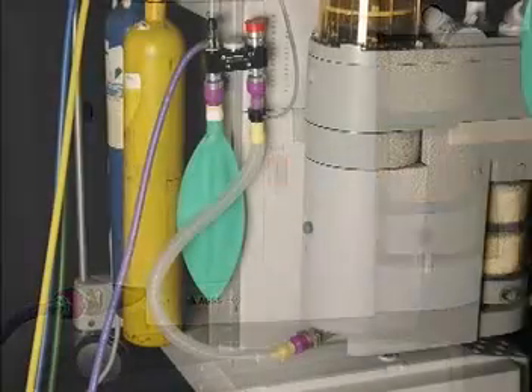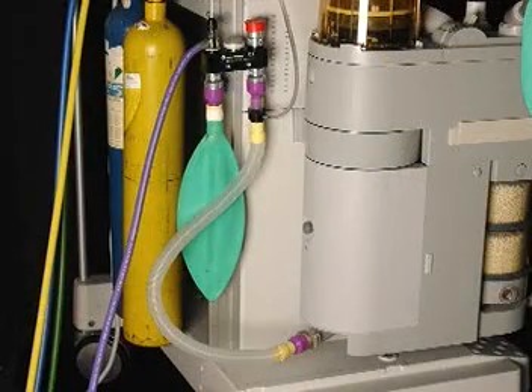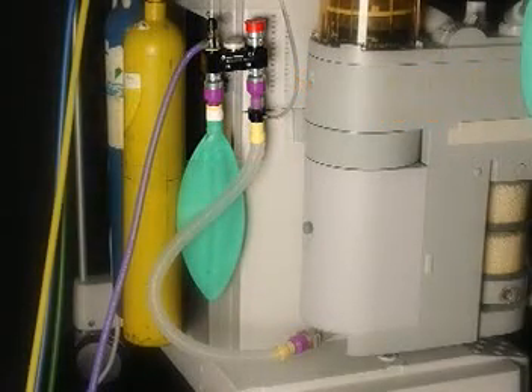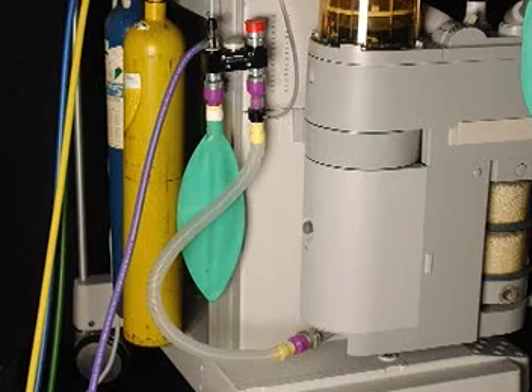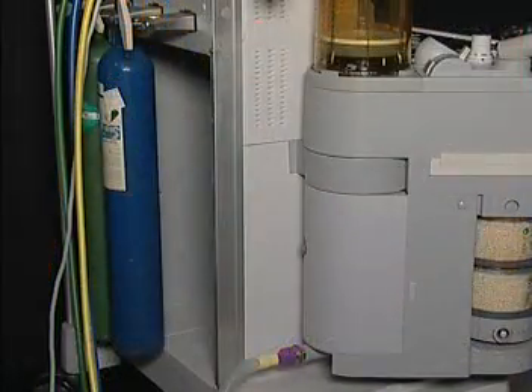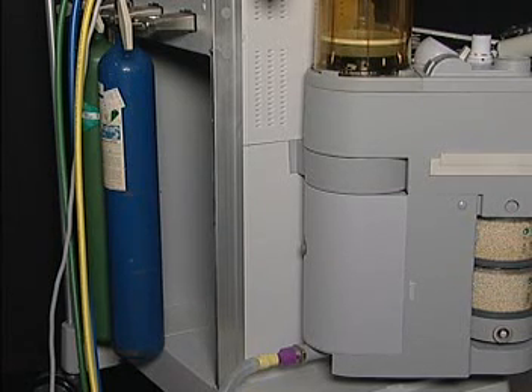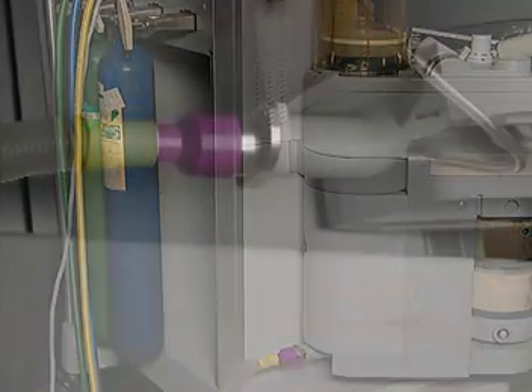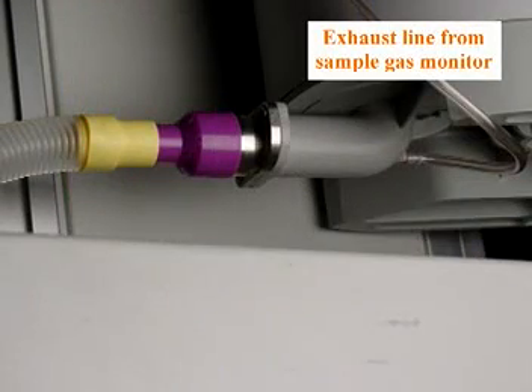For institutions with hospital vacuum flow capability less than 36 liters per minute, there is an option with a scavenger interface valve. This option requires the user to adjust the level of flow. If the installation requires interface to a scavenging system using room ventilation exchange, the option shown here is offered. A port is also offered for scavenging of the respiratory gas monitor sample.